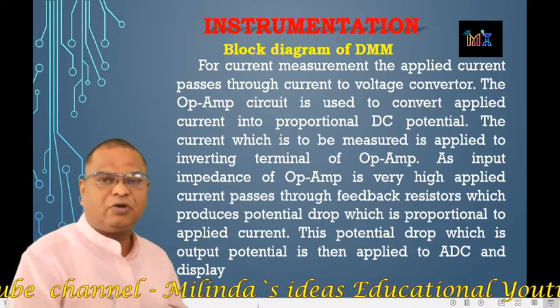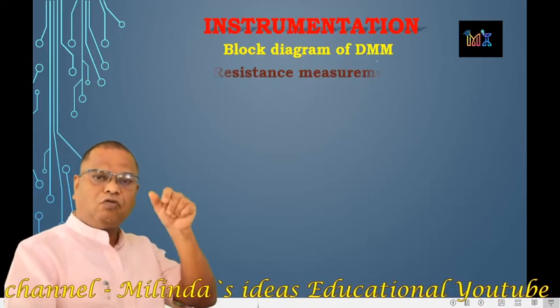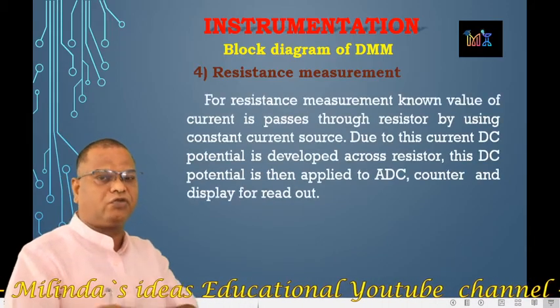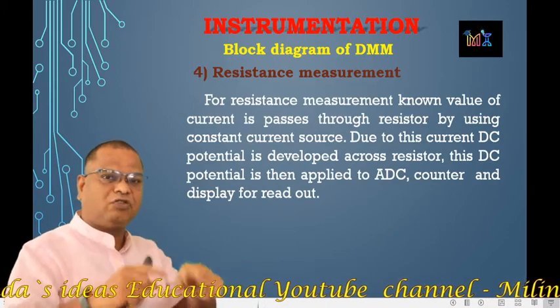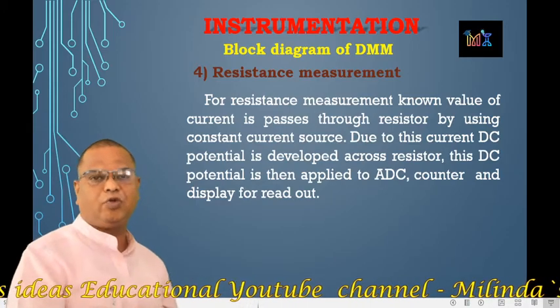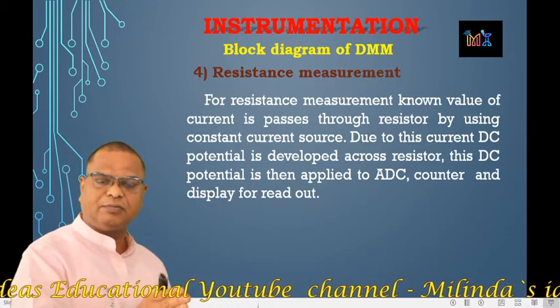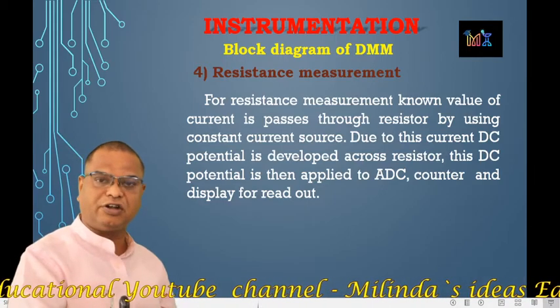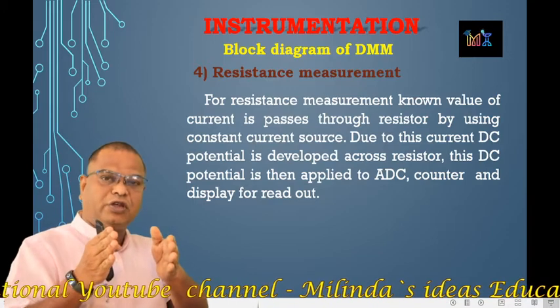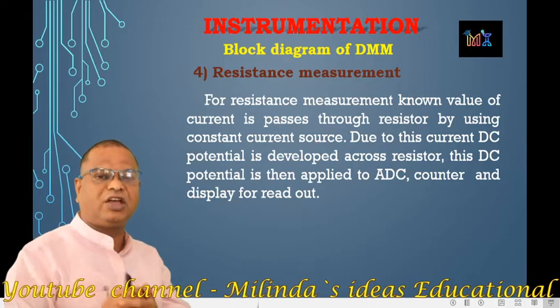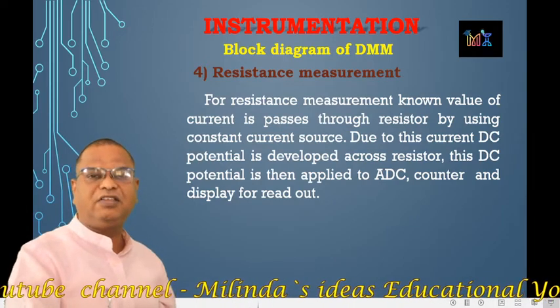The next block is resistance measurement. For the measurement of resistance, we require a constant current source. The constant current flows through the unknown resistance, and across that resistance, due to Ohm's law, a potential drop is developed. Since V = IR and the current I is constant, the potential drop is proportional to R. When the constant current flows through the resistance, we get a proportional potential drop, which is a DC potential.